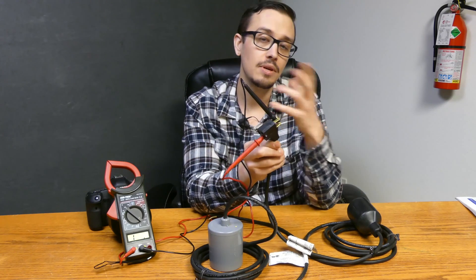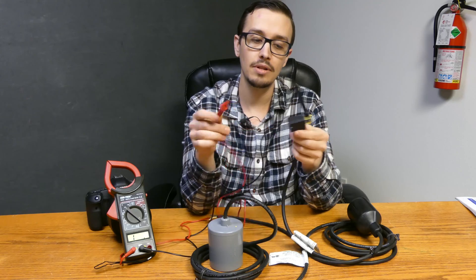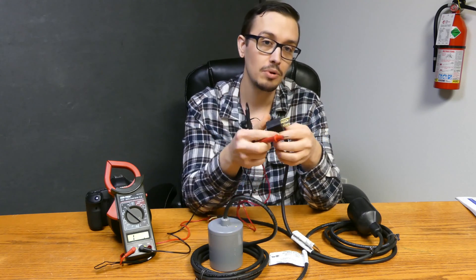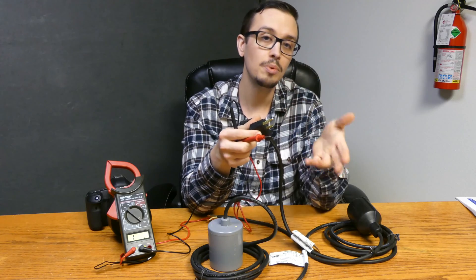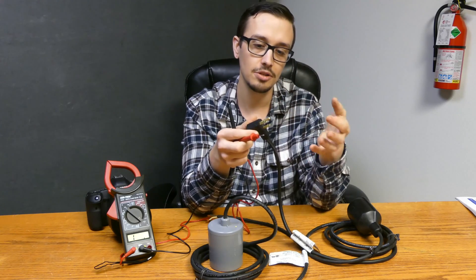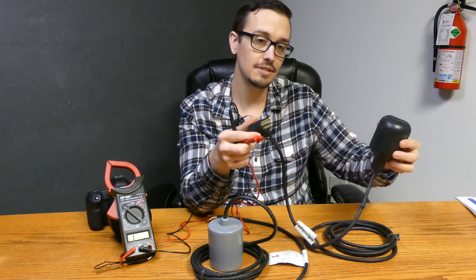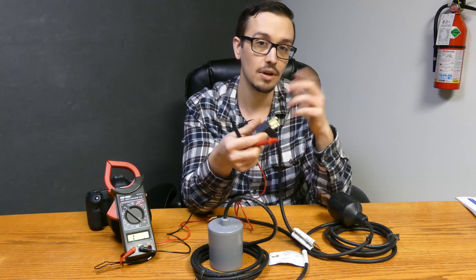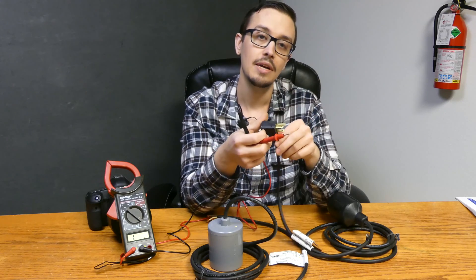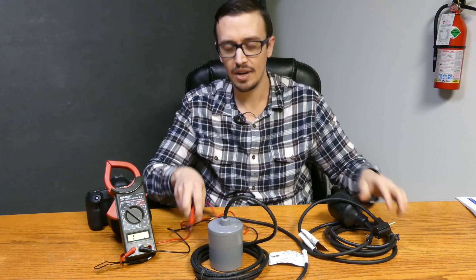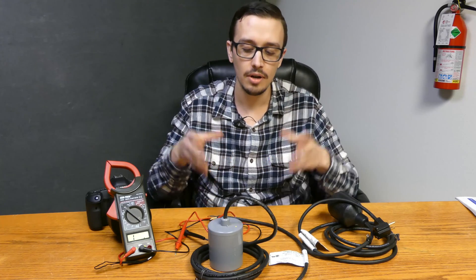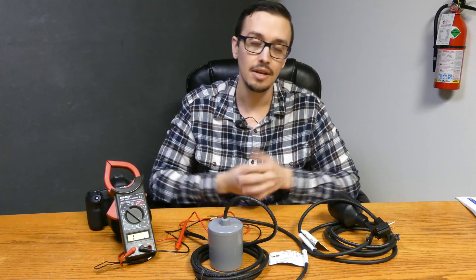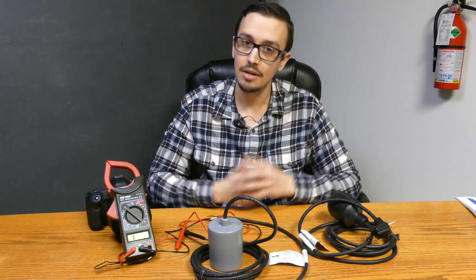You're able to quickly and easily determine if the float switch is working properly, open in the right position, closed in the right position. Obviously if I raised this and lowered it and the noise didn't shut up or I never got any noise at all, we've got a problem. So it's an easy way to tell if you've got anything to be concerned about. What we're testing for or what we're checking here is that the switch operates as expected. So keep that in mind.